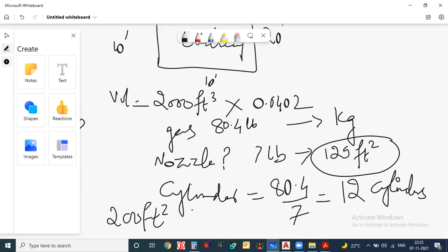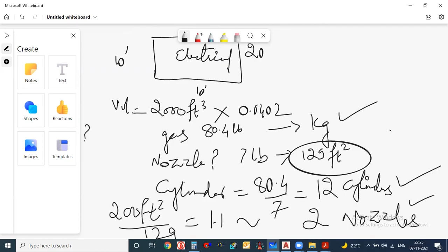So what we have done here is calculate how many cylinders required, how many nozzles required, and what is the gas quantity required. These 3 things we need to give to the vendor: the gas in kg, the number of cylinders, and the nozzles. They will cross check and do the calculation. For 2 nozzles we need 12 cylinders, as per this particular example, whatever the calculation they have shown according to this.